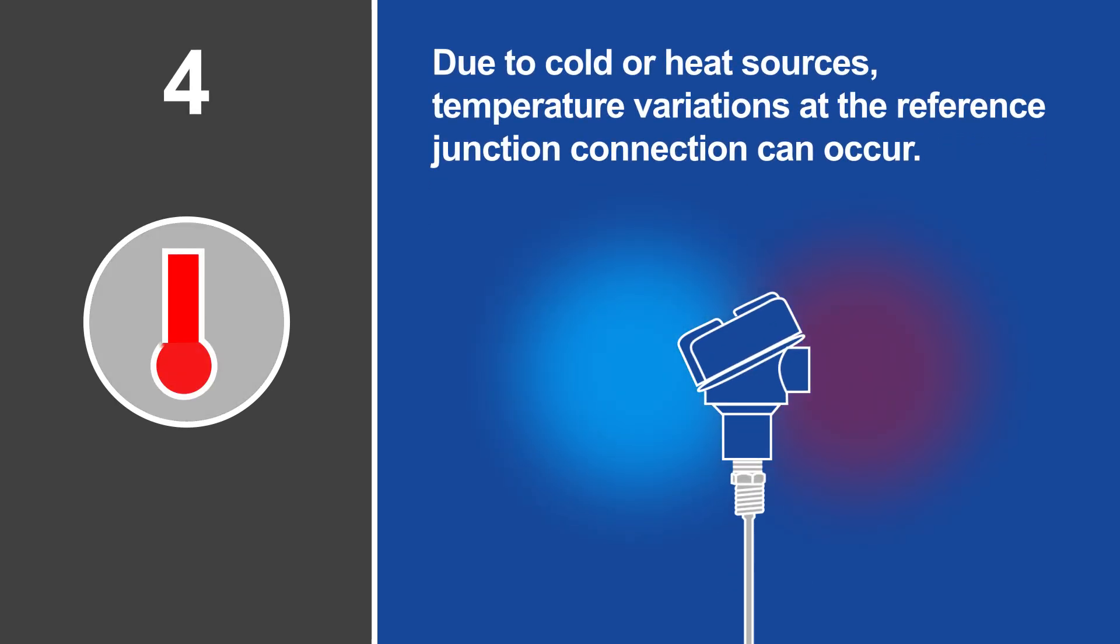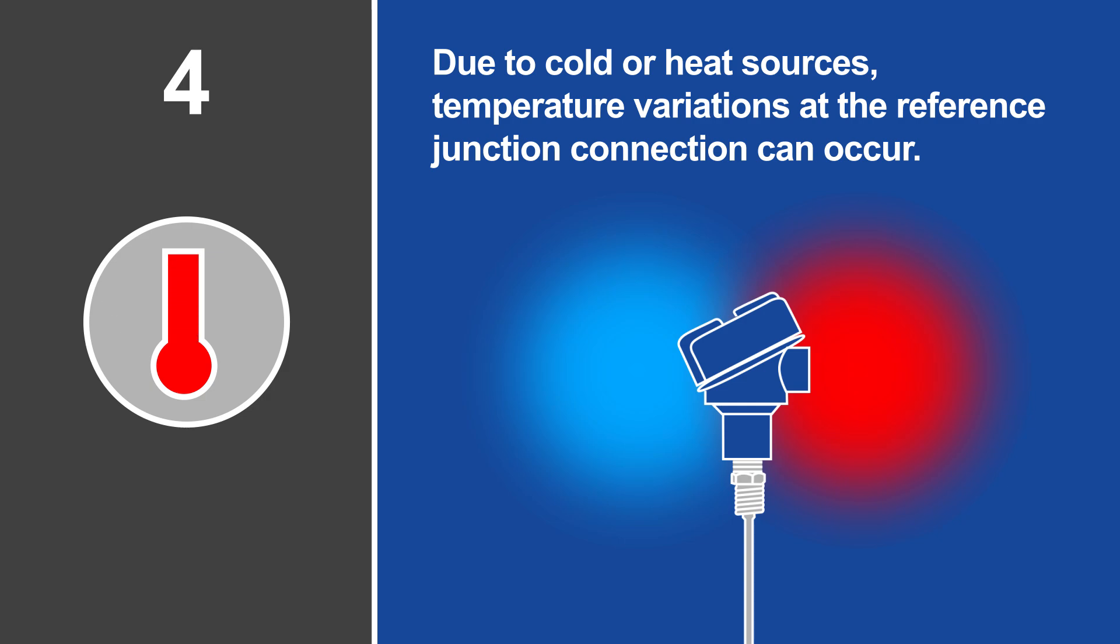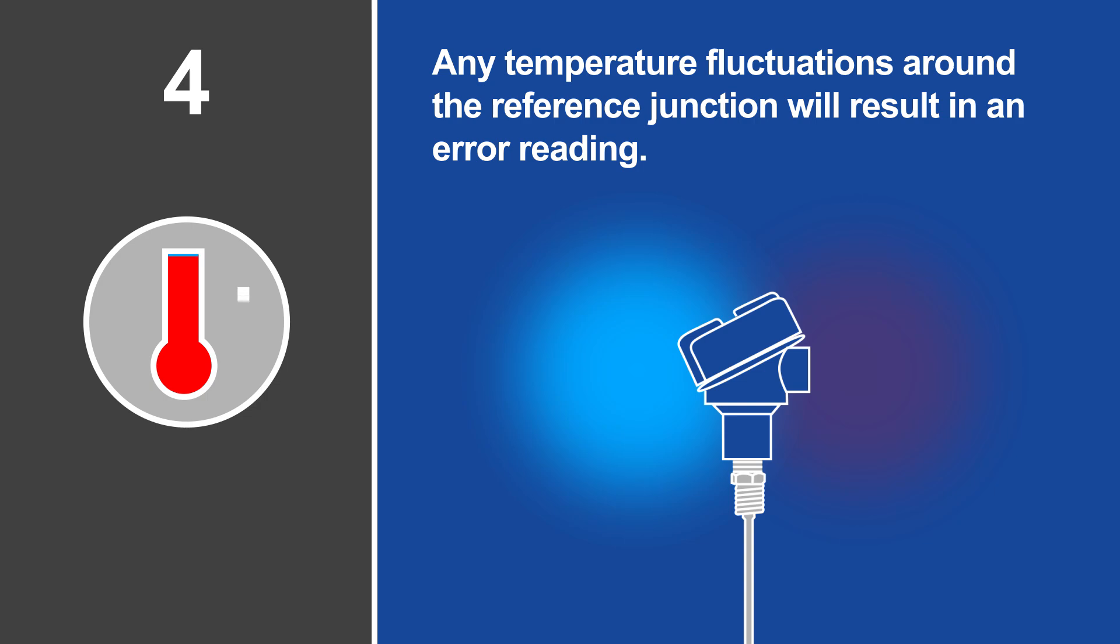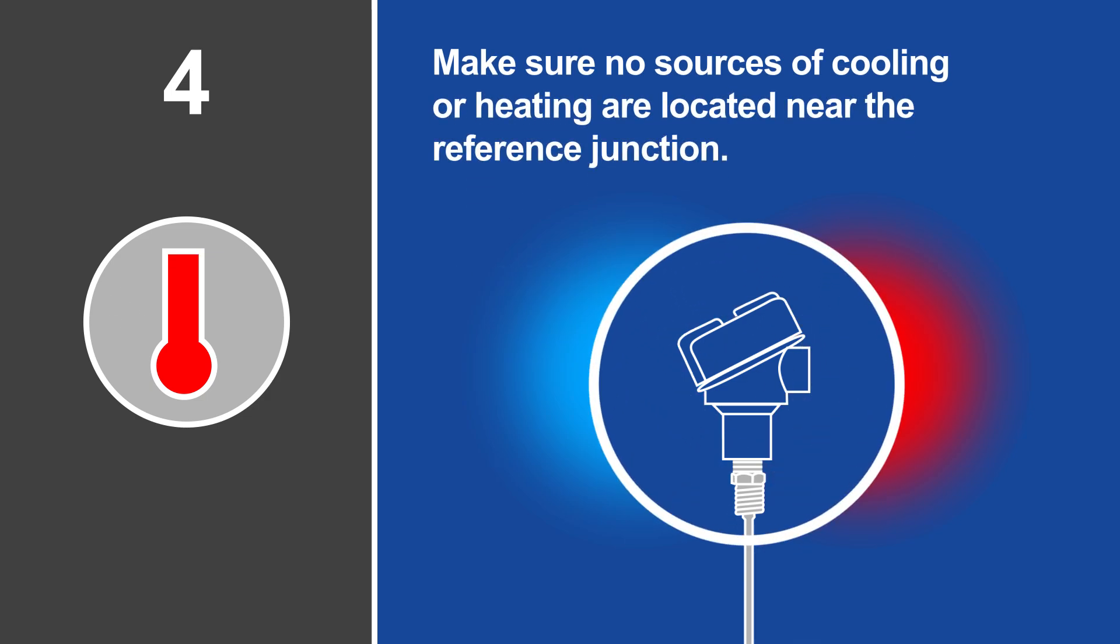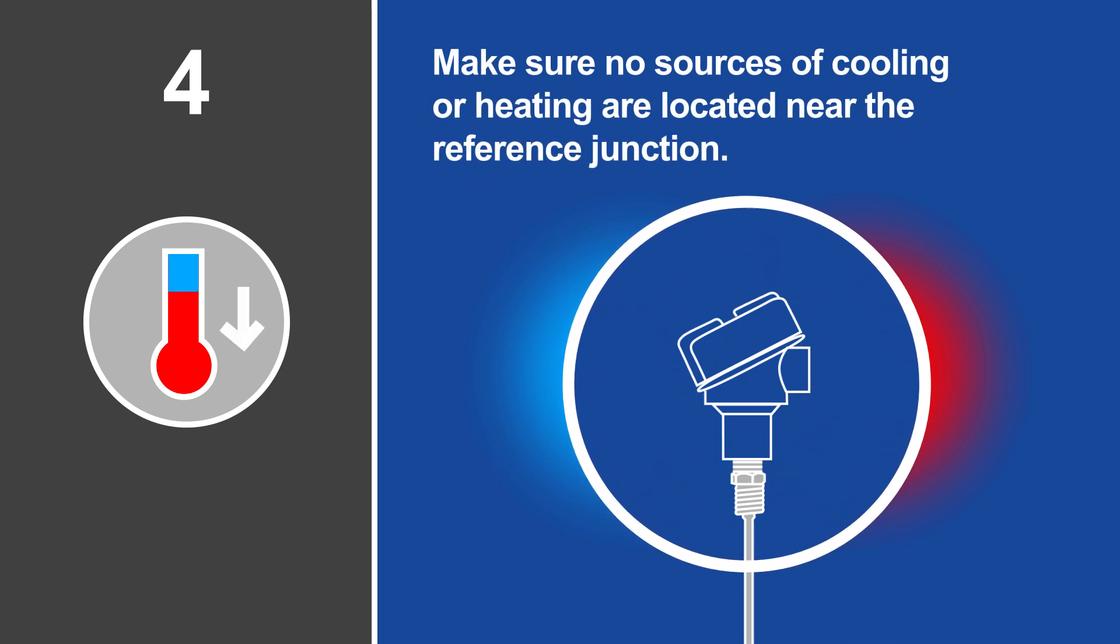Due to cold or heat sources, temperature variations at the reference junction connection can occur. Because a thermocouple measures temperature differentials, any temperature fluctuations around the reference junction will result in an error reading. The solution is to make sure no sources of cooling or heating are located near the reference junction. Simple insulation can also protect the junction from extreme temperatures.